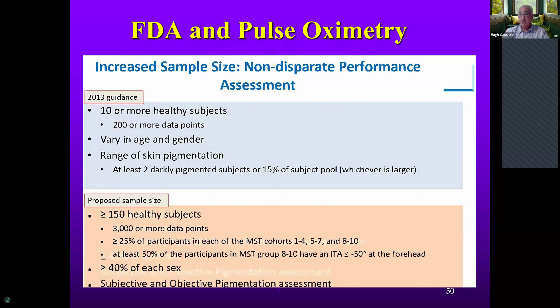And again, not just subjective measures, we want objective measures. And by the way, which we really haven't talked about, there are sex differences in terms of pulse oximeters. Women in general have smaller fingertips than men. And since this is a light-based technology, you can have more light scattering if you have more fingertip than if you don't. So we're going to require for the first time fair representation of gender. We want greater than 40% to be either men or women, so that when you make your calibration curve, you're accounting not just for skin pigmentation, but also for this light scatter, which you can get for varying finger sizes, which is different in males versus females. So this is how we're going to try to fix the problem moving forward.